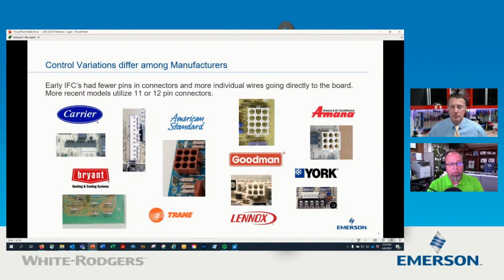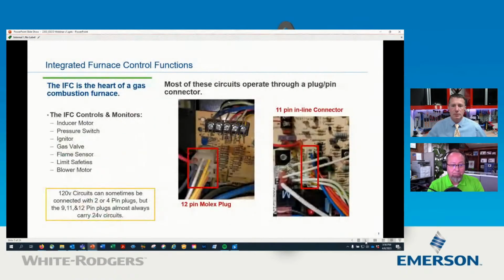You'll always find 24 volts in these. I don't know of hardly any instance where a manufacturer would put 120 volts in one of these plugs along with the 24 volts. The only exception to that rule is that the flame sense current signal can go through here, but that signal, the microamps coming from it, is lower than the 24 volt signal going through. So there's not a concern of having too much of a charge through that.